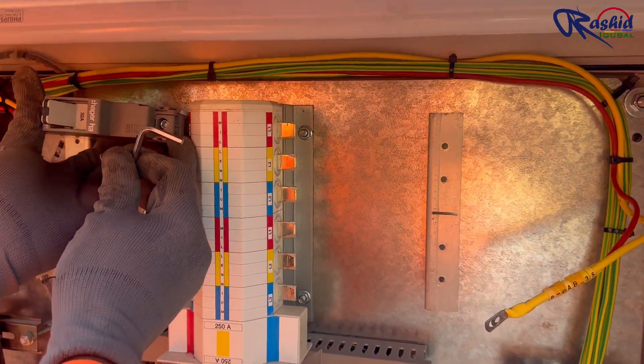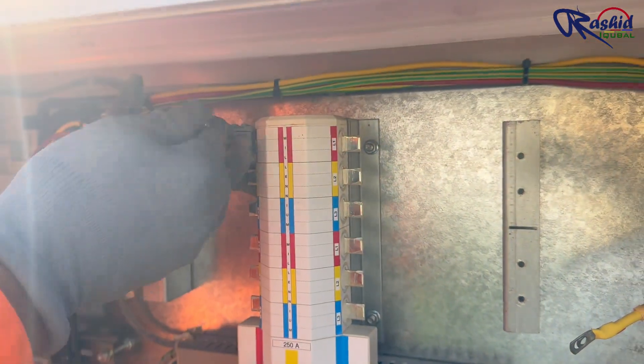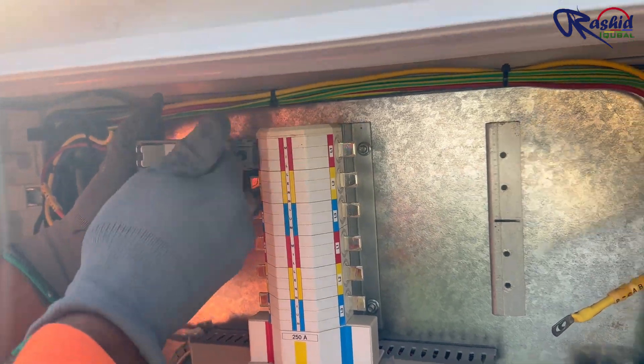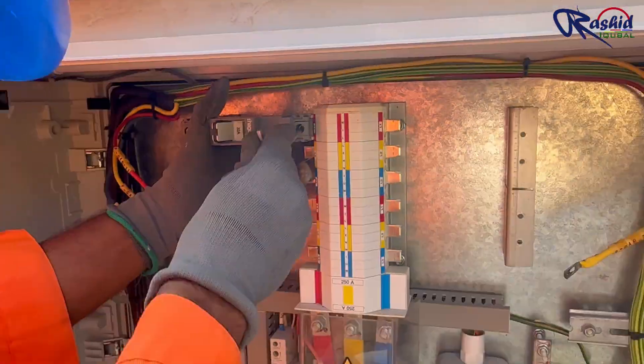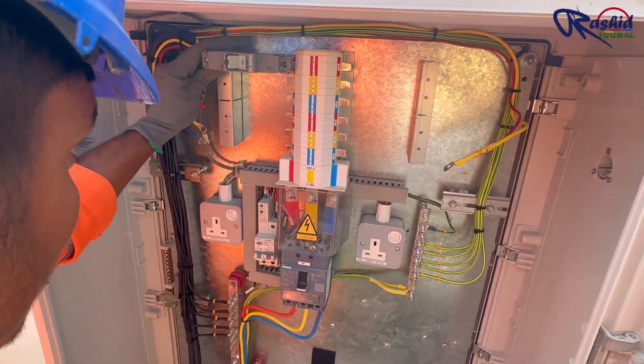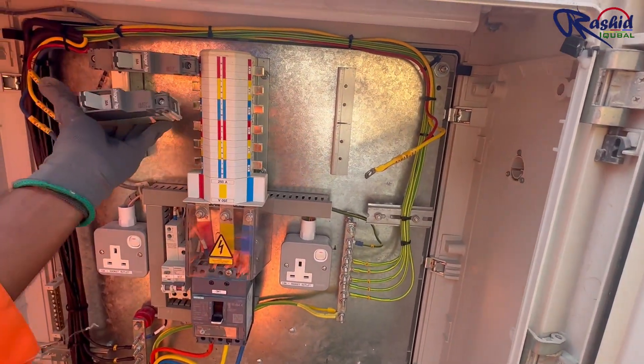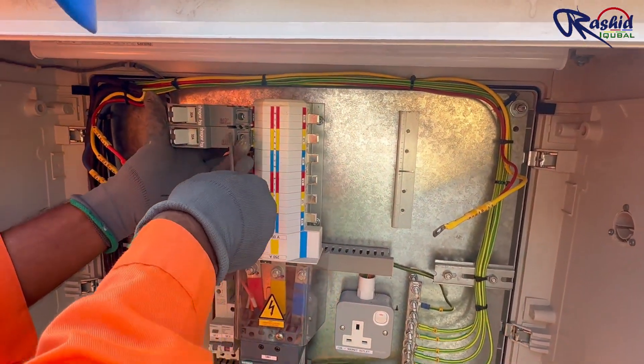Now he is installing single pole MCBs in every phase. He is tightening the input terminal of the MCB with the bus bar. In the same way, he will install all the breakers.